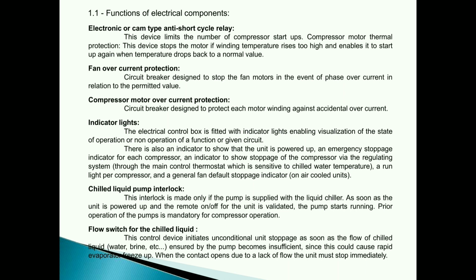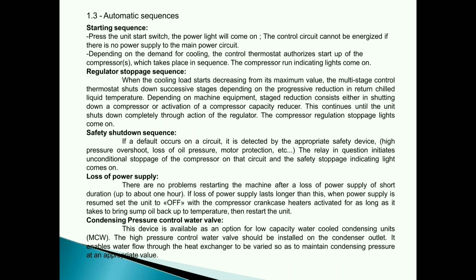Flow switch for the chilled liquid. This control device initiates unconditional unit stoppage as soon as the flow of chilled liquid, water, brine, etc., ensured by the pump becomes insufficient, since this could cause rapid evaporator freeze up. When the contact opens due to a lack of flow, the unit must stop immediately.